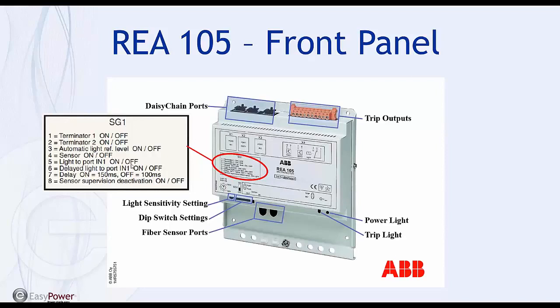You always have this switched off, and then you can have breaker failure. You can delay the light signal back to the main if you have a breaker failure. The idea here is that you want to achieve selectivity, so you don't want to send light back to the main unit. You do want some discrimination for downstream arcing faults. Then you have your pre-programmed breaker failure delay, and you have your loop supervision.